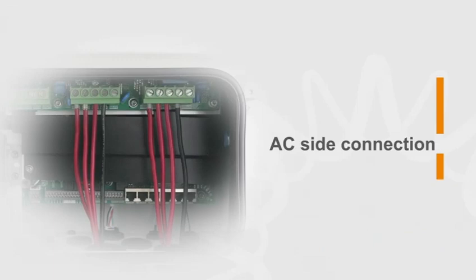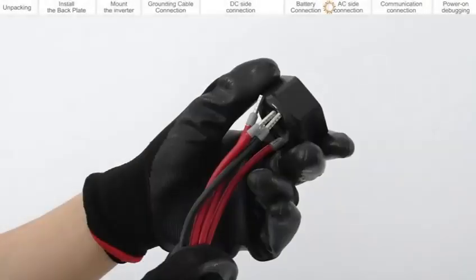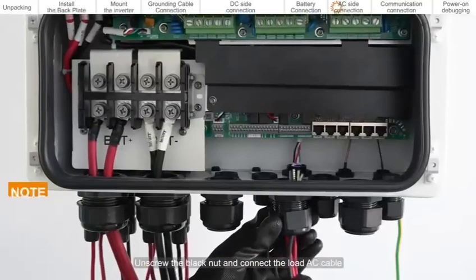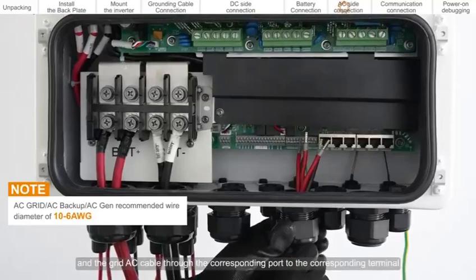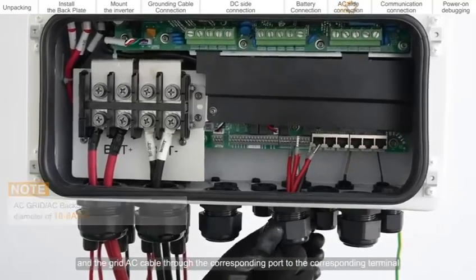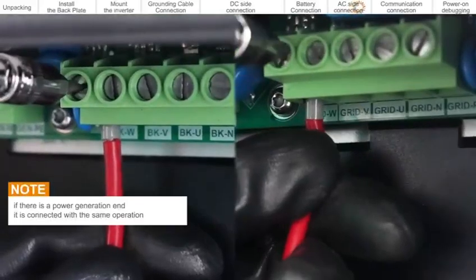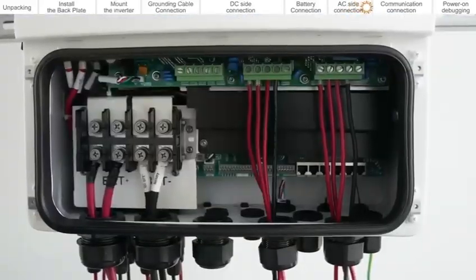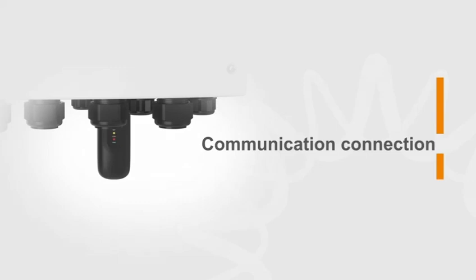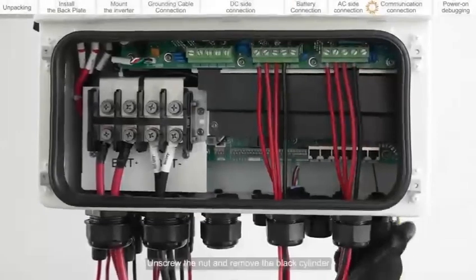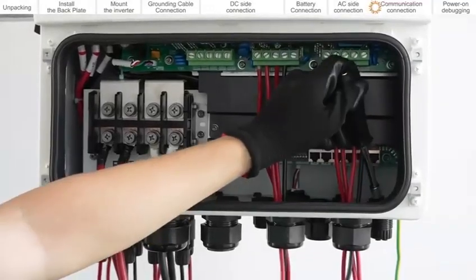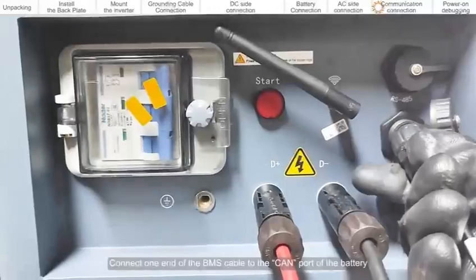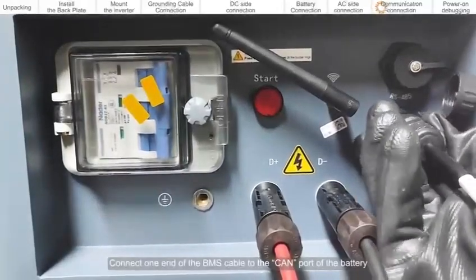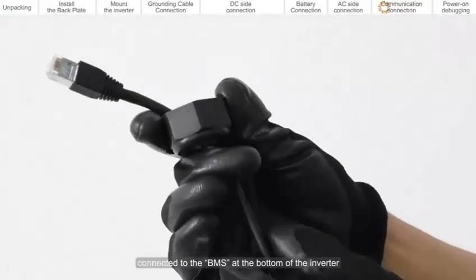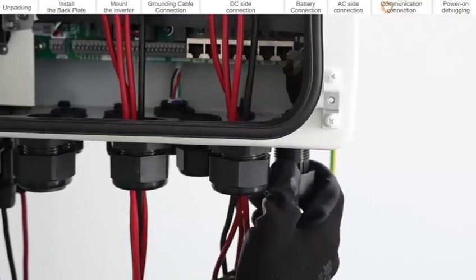AC side connection. Unscrew the black nut and connect the load AC cable and the grid AC cable through the corresponding port to the corresponding terminal. Communication connection. Unscrew the nut and remove the black cylinder. Connect one end of the BMS cable to the CAN port of the battery, and the other end to the BMS port at the bottom of the inverter.